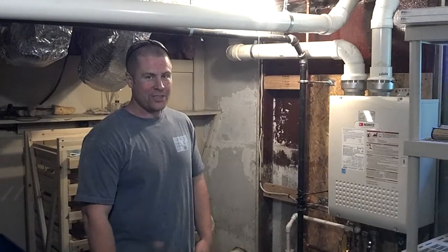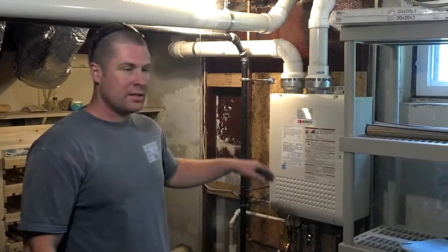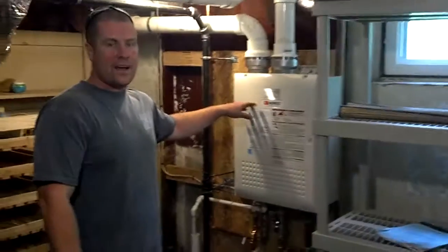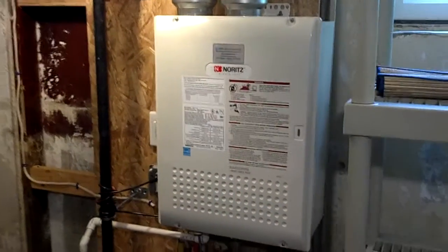Bill Duggan, Corey Hills Plumbing and HVAC Incorporated. We did an oil to gas conversion. They had an existing Weil-McLain steam-fired boiler with recessed convector style radiators upstairs on the first floor. The second floor was already done for forced hot air. We put in a Noritz NIC-111-DV tankless hot water heater.